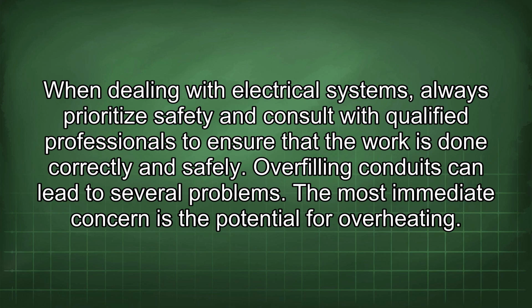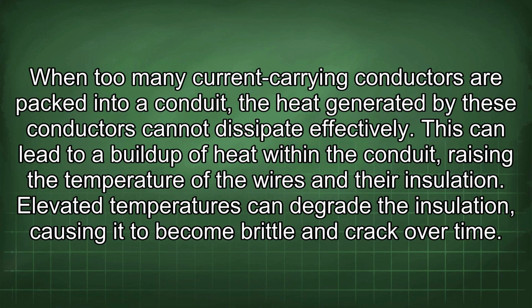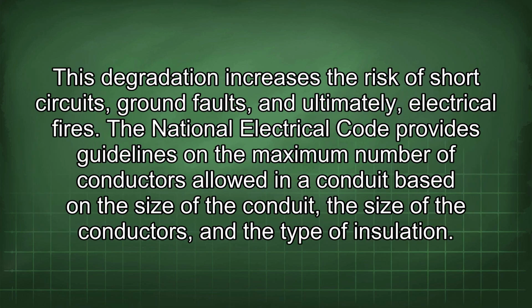The most immediate concern is the potential for overheating. When too many current-carrying conductors are packed into a conduit, the heat generated by these conductors cannot dissipate effectively. This can lead to a buildup of heat within the conduit, raising the temperature of the wires and their insulation. Elevated temperatures can degrade the insulation, causing it to become brittle and crack over time. This degradation increases the risk of short circuits, ground faults, and ultimately, electrical fires.